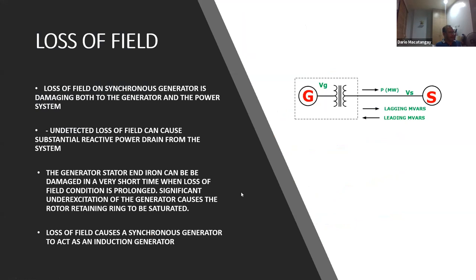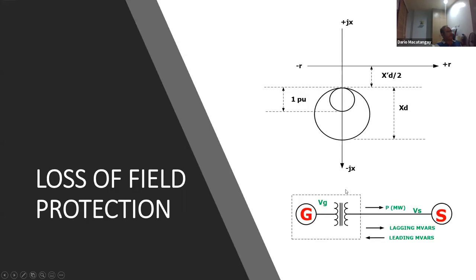The generator stator end iron can be damaged in a very short time if the loss of field condition is prolonged. Significant under-excitation of the generator causes the rotor retaining ring to be saturated. Loss of field causes a synchronous generator to act as an induction generator. So that means it's not synchronized anymore when it's operating as an induction generator. The loss of field is implemented using a Mho characteristic.